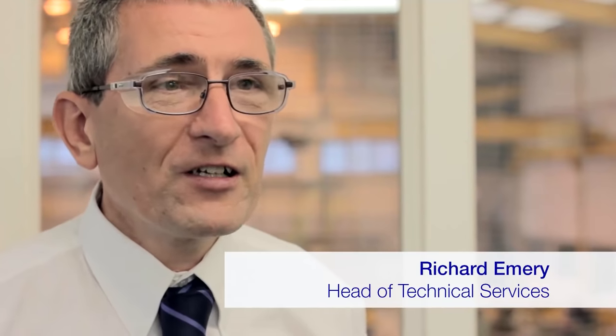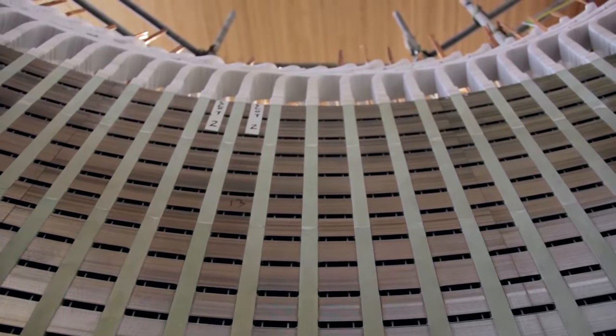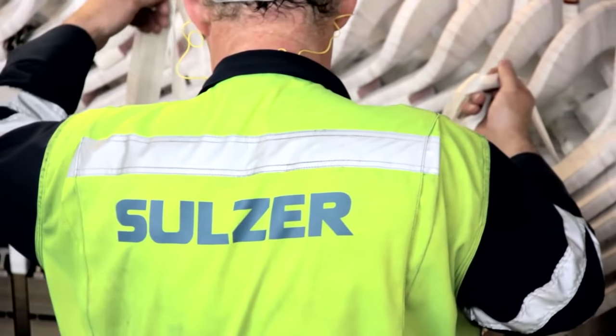The aim is to replace the stator completely — the laminations and the coils — re-insulate the bus bars, and refurbish the rotor. What we've done is developed and designed a new core which is a whole core. It's one unit, and this should cancel out all the vibration problems that we are receiving just now.